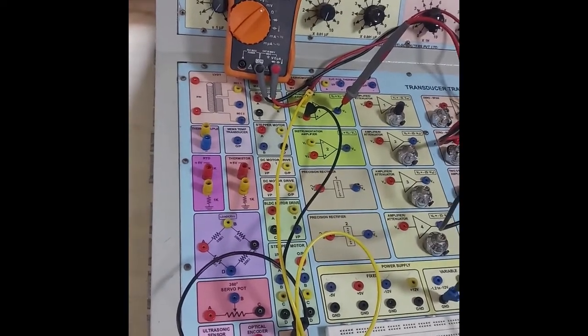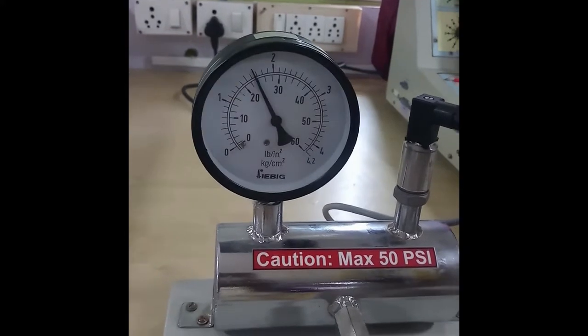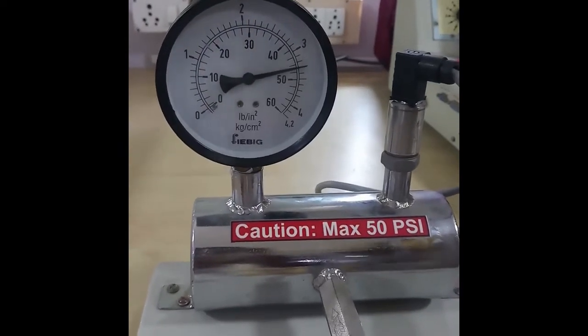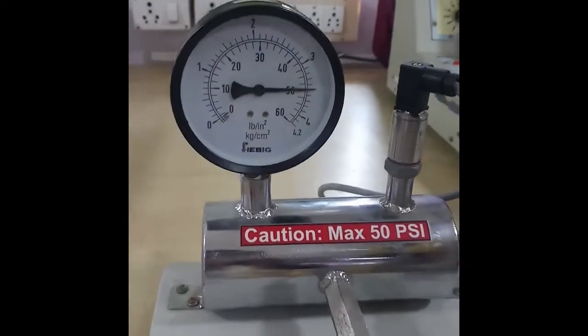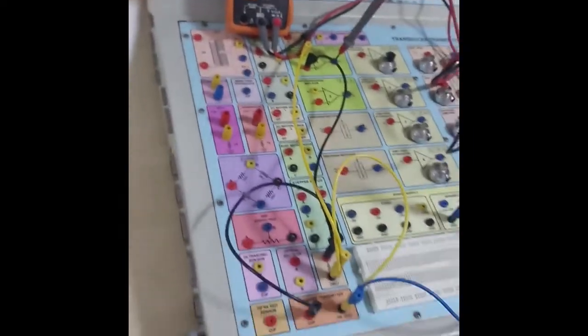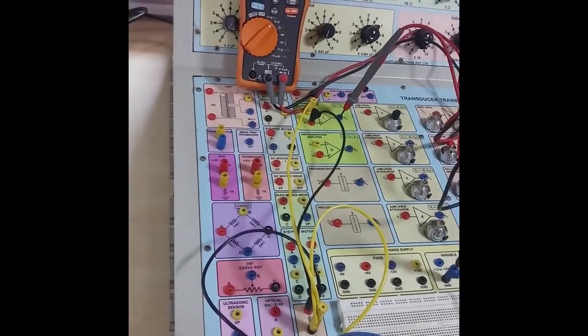Now I am going to apply the maximum pressure of 50 psi. By pressing the foot pump, I am giving maximum 50 psi. For 50 psi, if you see the multimeter, we are getting 4.40 volts. Due to some leakage, the values keep decreasing, but it is 4.40 volts for 50 psi. Note down: for 50 psi, we got 4.4 volts.